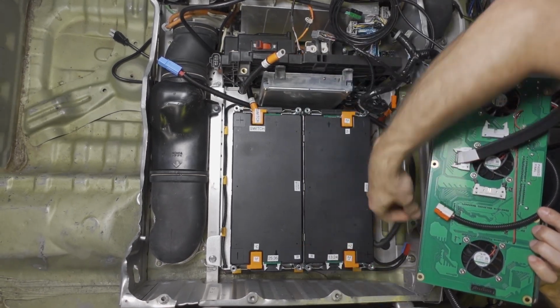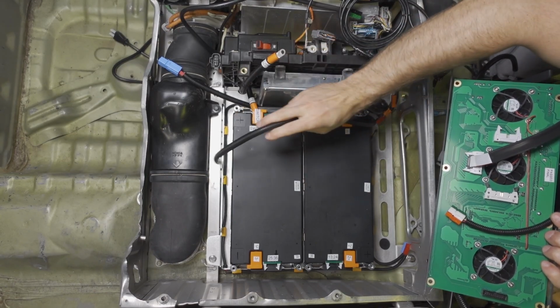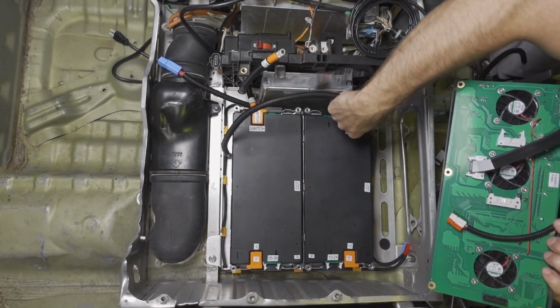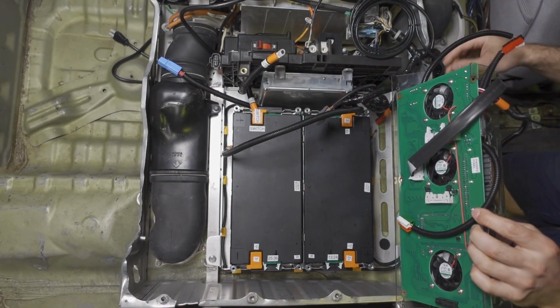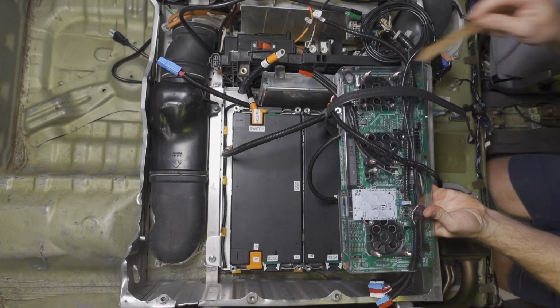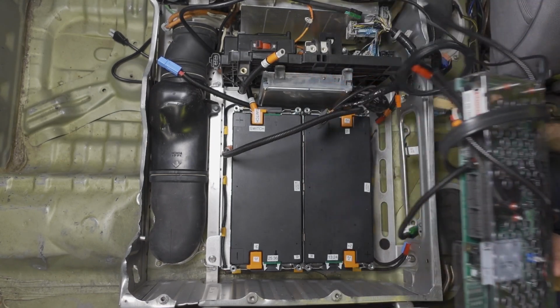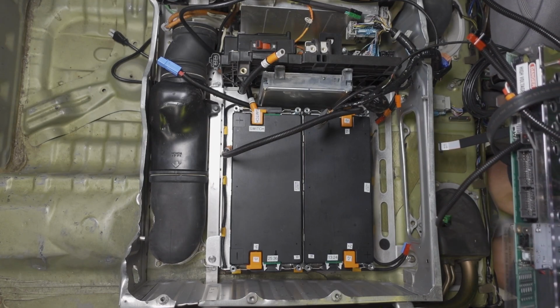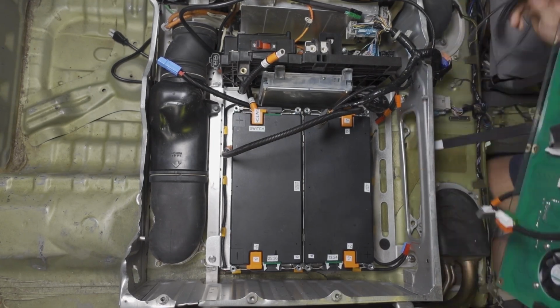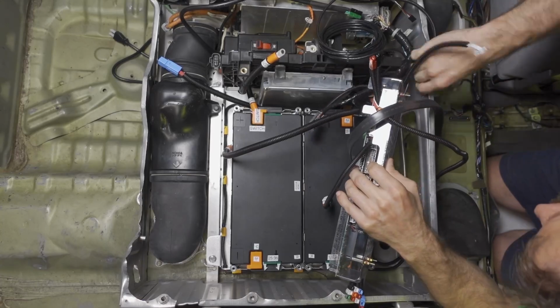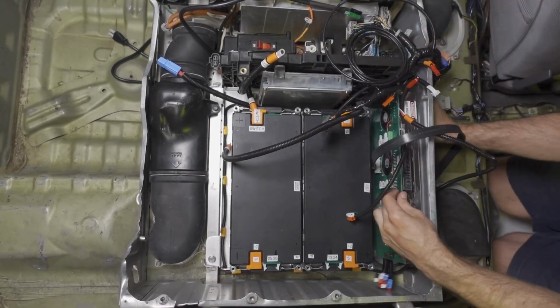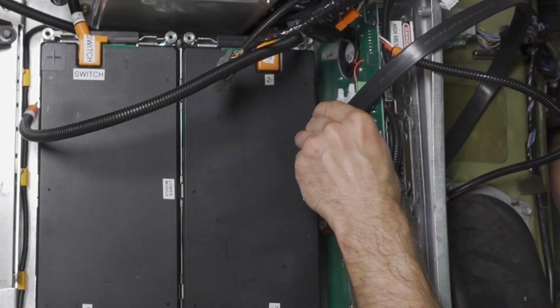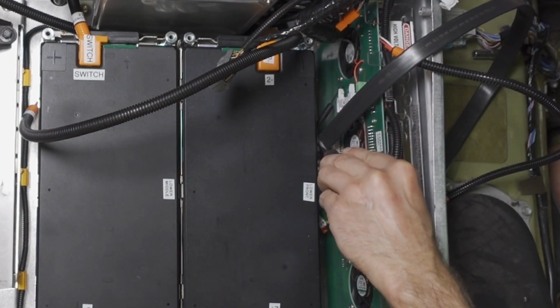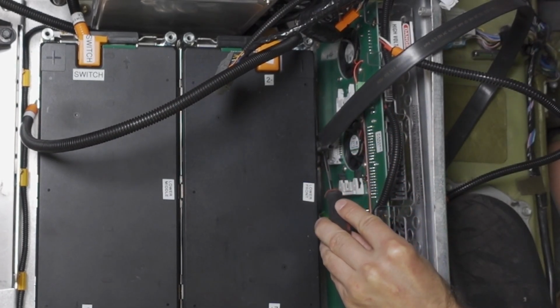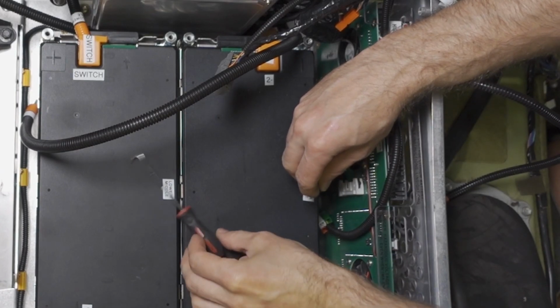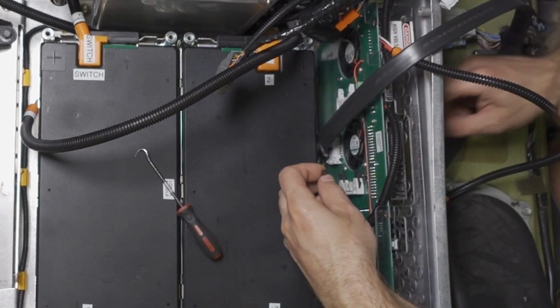Before we put it in, we need to pull this cable and just pick it up out of the way. It's not hooked up to anything yet, so it doesn't matter if it touches anywhere. And we're going to put these 4 studs into these 4 holes, just like we did previously when we were checking our fitment. Before you install the nuts, make sure that the temperature cable here is not crushed. It's attached to the lower tray. You probably can't see it here.